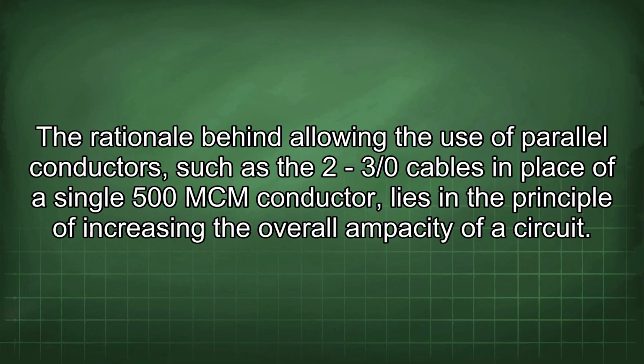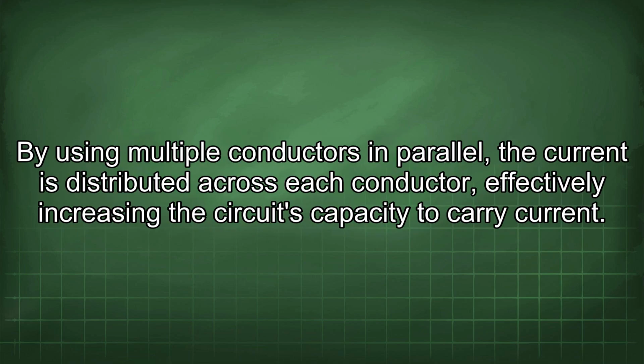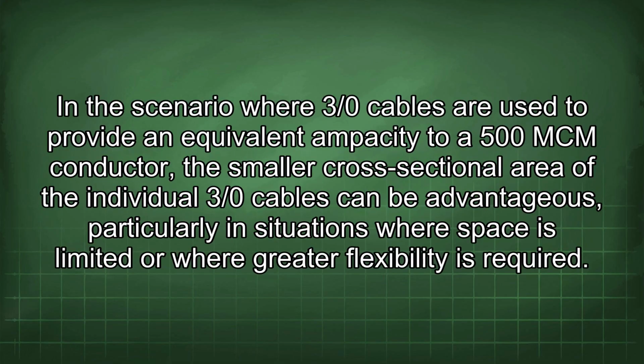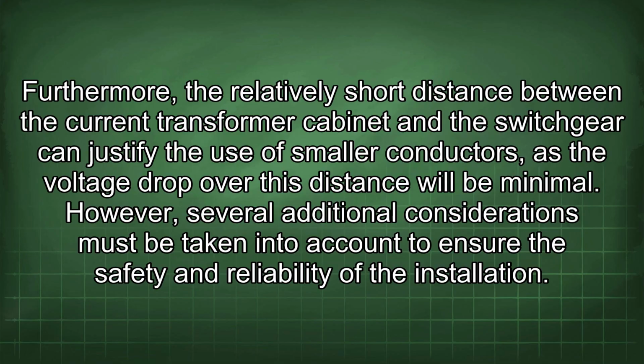The rationale behind allowing the use of parallel conductors, such as the two 3/0 cables in place of a single 500 MCM conductor, lies in the principle of increasing the overall ampacity of a circuit. By using multiple conductors in parallel, the current is distributed across each conductor, effectively increasing the circuit's capacity to carry current. In a scenario where 3/0 cables are used to provide an equivalent ampacity to a 500 MCM conductor, the smaller cross-sectional area of the individual 3/0 cables can be advantageous, particularly in situations where space is limited or where greater flexibility is required. Furthermore, the relatively short distance between the current transformer cabinet and the switchgear can justify the use of smaller conductors, as the voltage drop over this distance will be minimal.